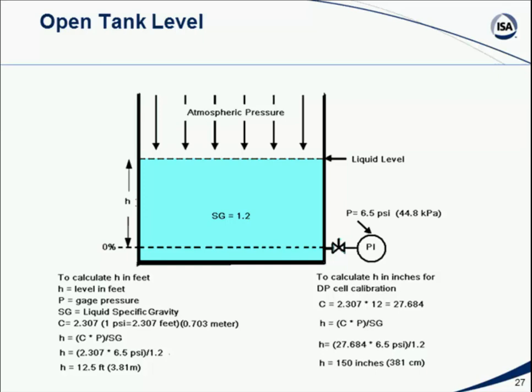Well, if you think about it, how can that be 6.5 psi? I've already told you that the atmosphere is pressing down with 14.69 psi. So it's got to at least be that, right? Because we can't have less than atmospheric pressure. Well, here's where we have to talk about how we take pressure measurements. That instrument that we show hanging off the bottom of the tank, that PI, that pressure indicator, is probably a pressure differential transmitter. In other words, it is a device that is not measuring the absolute pressure. It's measuring the pressure difference between one side and the other side.